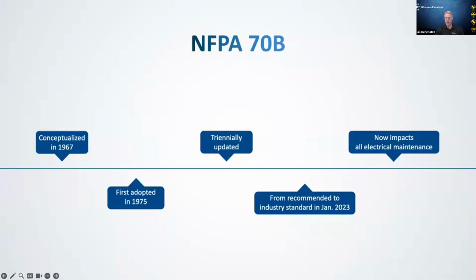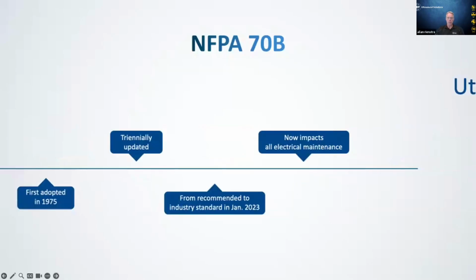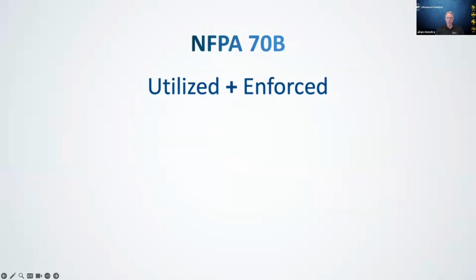What that means is simple but powerful. NFPA 70B is no longer just guidance. It's now the benchmark that defines how electrical maintenance must be performed. Its scope impacts virtually every aspect of electrical system maintenance today. So as of January 2023, NFPA 70B transitioned from a recommendation to a standard, and a standard that can be enforceable.